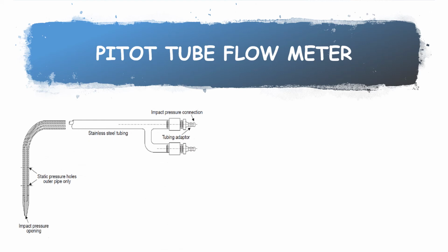Now this diagram tells you how a typical Pitot tube would look. The total pressure developed at the point where the flow is stagnated is assumed to occur at the tip of the Pitot tube or at a specific point on a bluff body immersed in a stream. This tube causes practically no pressure loss in the flow stream. It is normally installed through a nipple inside the pipe.